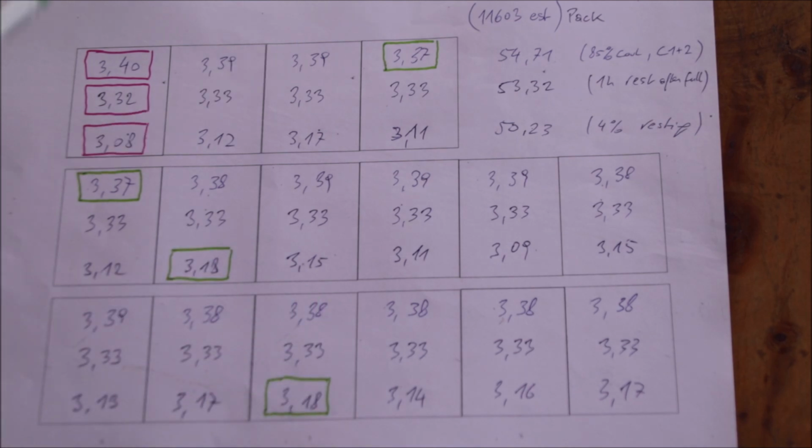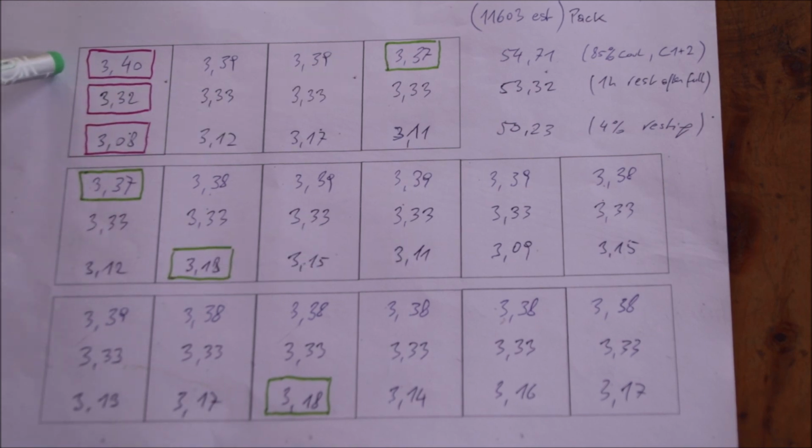So without any tester, by doing measurements like this, you can easily see immediately where your weakest cell string is, and this is, as you can see, exactly that cell string which we had to correct last time. These measurements can tell you immediately that that cell string has a lower capacity than all others, because it will be fastest on the up and fastest on the low.